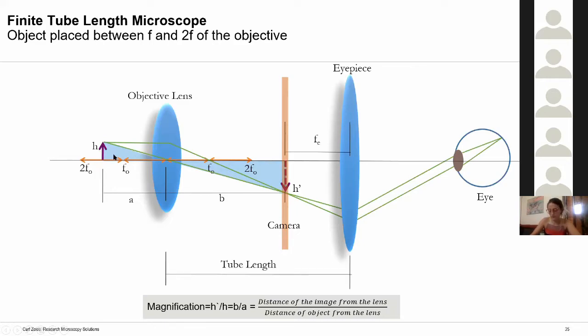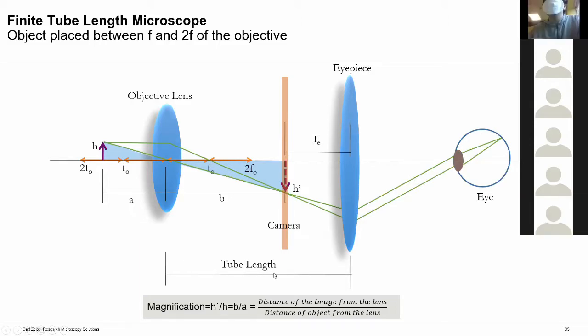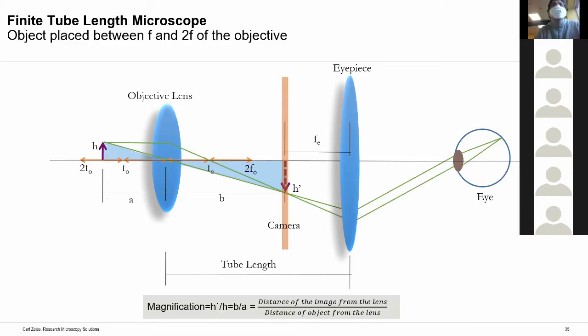In the finite tube length microscope, the distance between the objective and eyepiece is called the tube length. Once the magnification of the system is fixed, this tube length remains the same and cannot be changed. This created some complications in initial microscopy design, so modern microscopes do not use the finite tube length configuration. Modern microscopes use what is called an infinite tube length configuration.